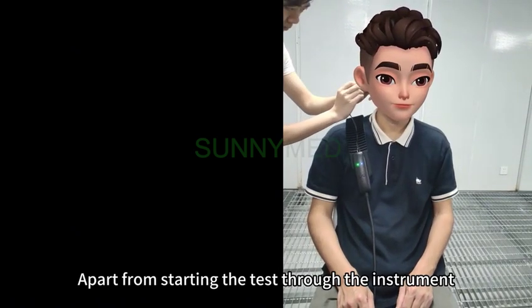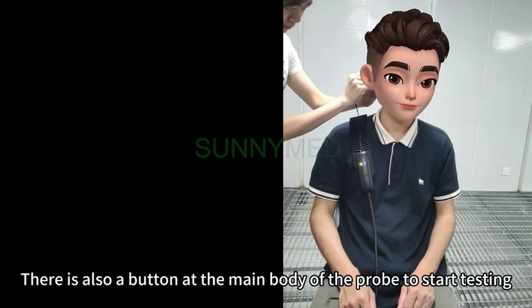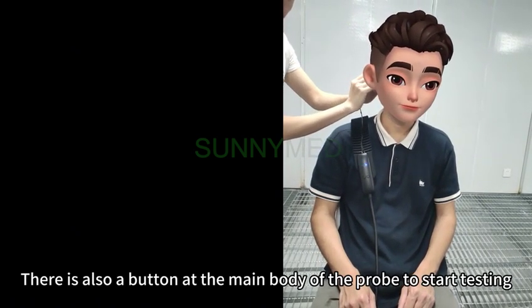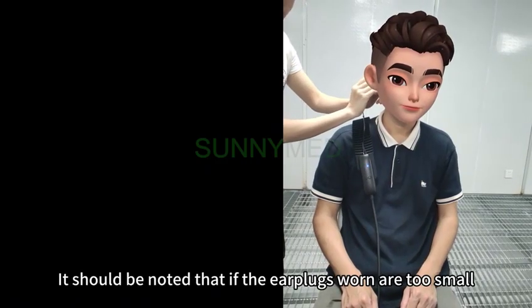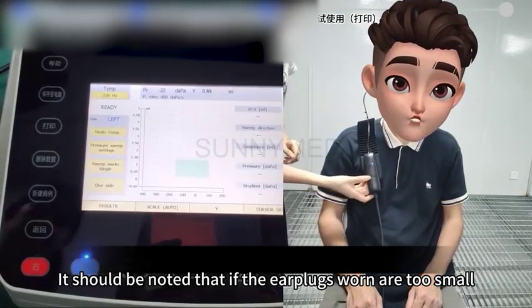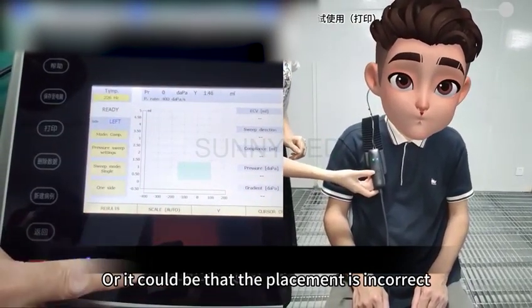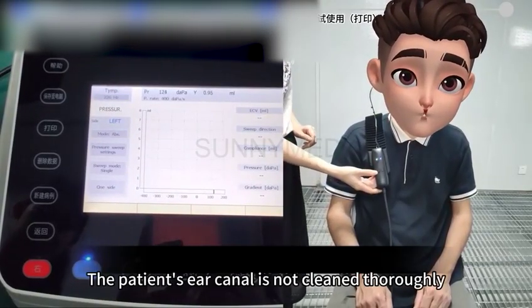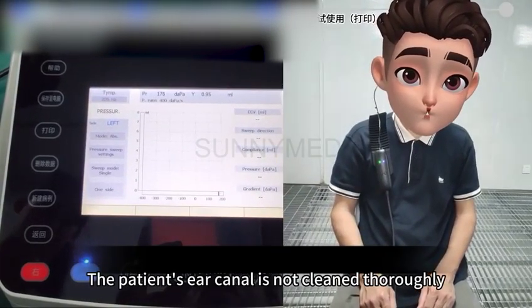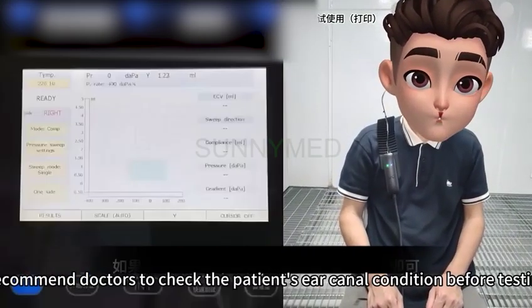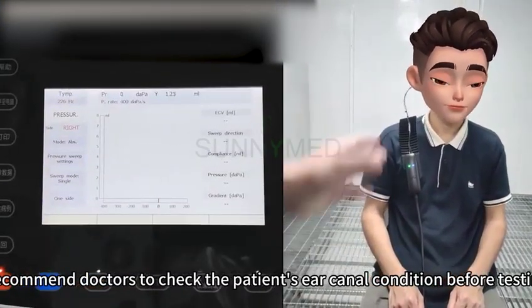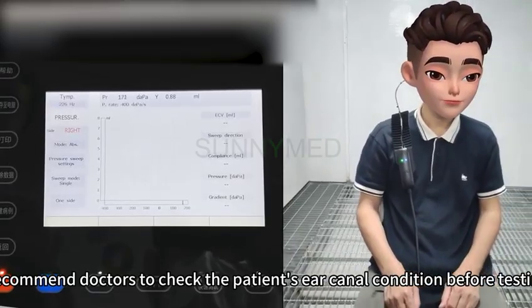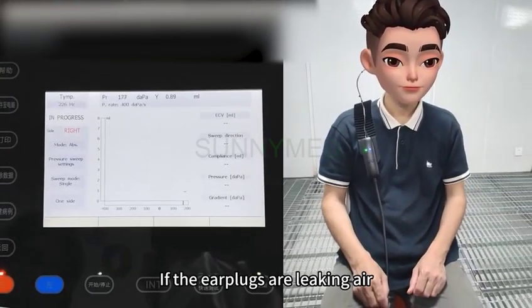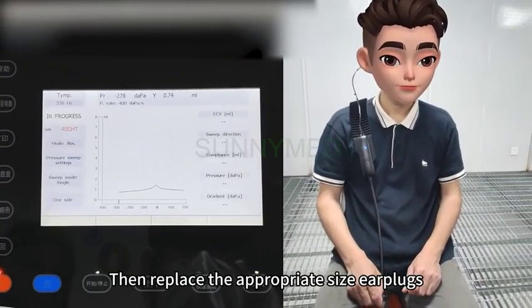Apart from starting the test through the instrument, there is also a button on the main body of the probe to start testing. It should be noted that if the earplugs worn are too small, or the placement is incorrect, or the patient's ear canal is not cleaned thoroughly, the instrument will display test failure. Recommend doctors to check the patient's ear canal condition before testing. If the earplugs are leaking air, then replace them with the appropriate size.